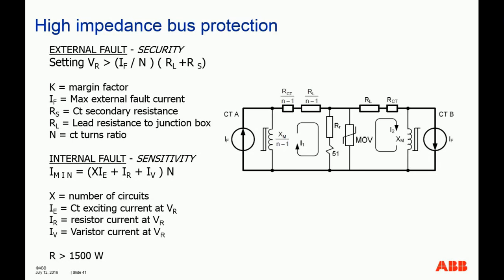Actually, some vendors suggest using an 86 lockout relay in parallel as well. That means as soon as the relay operates, the lockout relay contact will close and short out the high voltage branches.